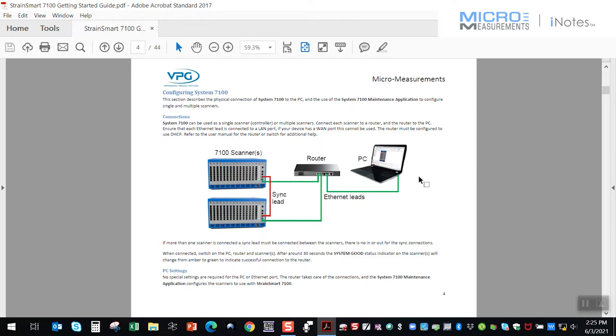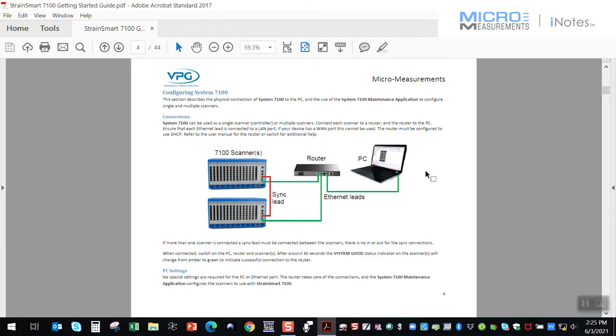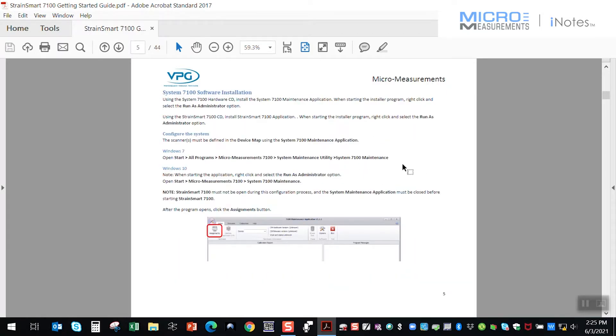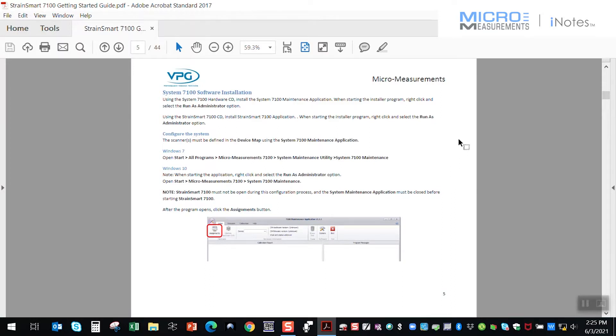The first thing that we're going to do is set up what's called a maintenance utility software. And a lot of folks will bypass that and try to install and run StrainSmart right out of the box and fail. So if you follow the steps in this Getting Started Guide, it will show you this physical connectivity here using that smart router, and then walk you through what's referred to as the maintenance utility software to establish the communications between your PC and the scanner.